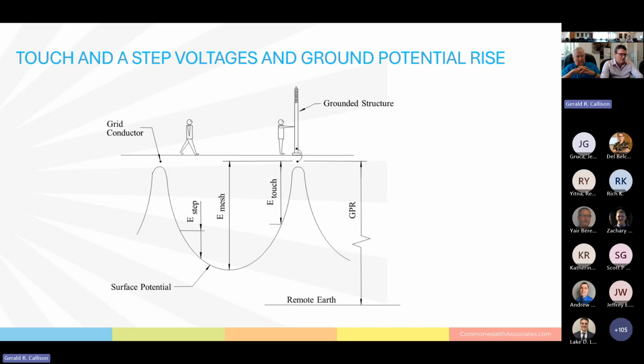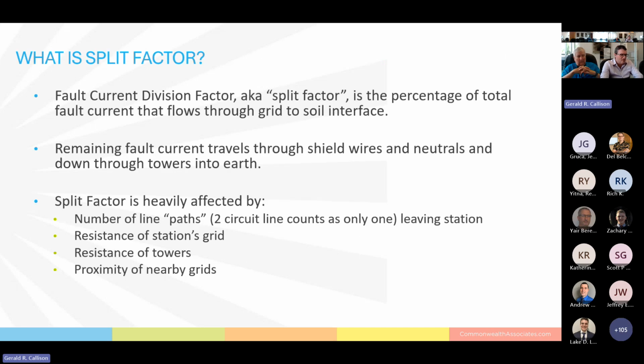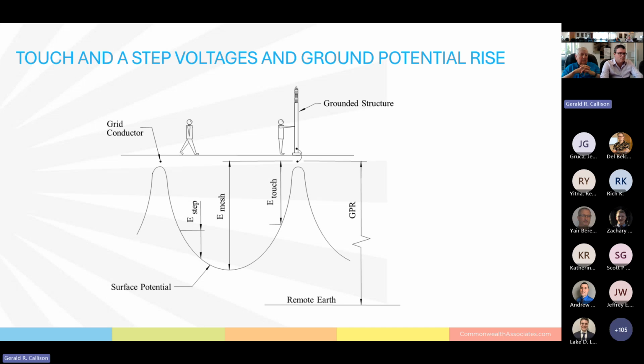So as the potential of the ground grid rises, there's a difference between the potential of the ground grid and the potential of the surface of the earth where a person's feet are located. And so that difference between the surface of the earth and the potential of a grounded object connected to the ground grid is touch potential. So that's touch and step potential. And fundamentally, ground grids are controlling touch and step potential so that they stay beneath levels that are determined to be safe for the application.